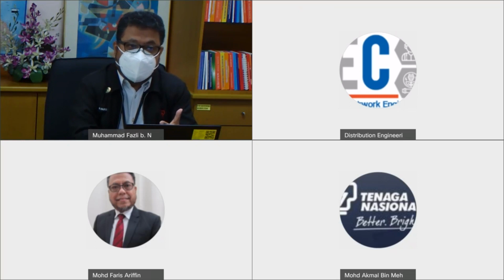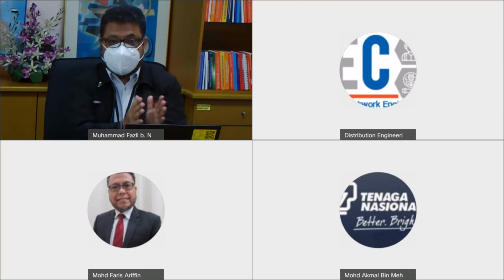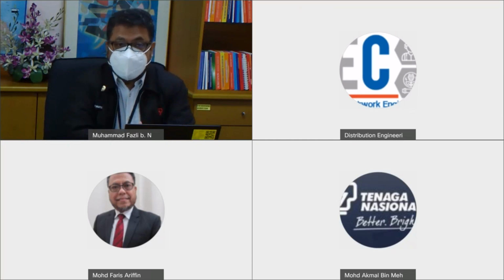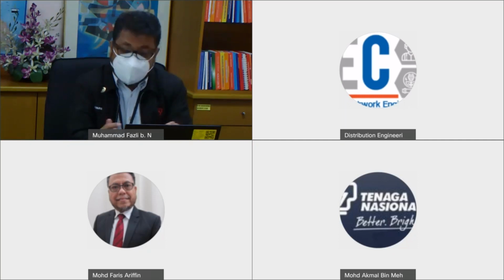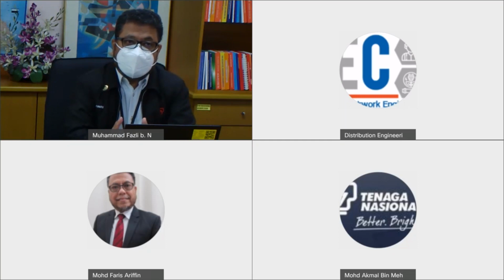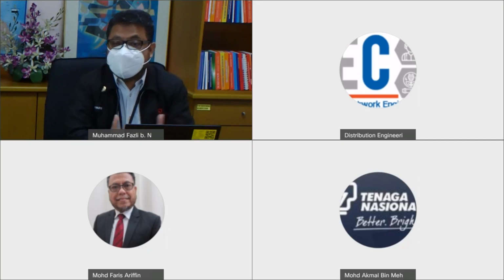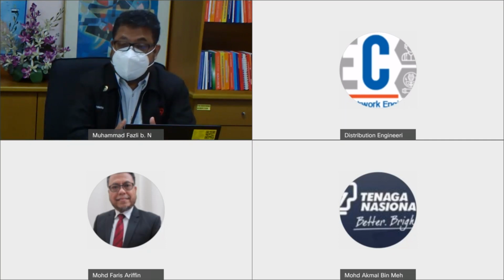And we have to also make sure, because we have the solid insulation and the air insulation, that the arcing horn is also properly installed at 42 cm minimum gap, so that we allow the flashover to occur across the gap. So that we mitigate the interruption of the overhead line from permanent interruption, causing longer loss of supply to our customer, to transient tripping, where it is only occurring momentarily within seconds, and we can restore the supply very fast, within 10 seconds, for example.